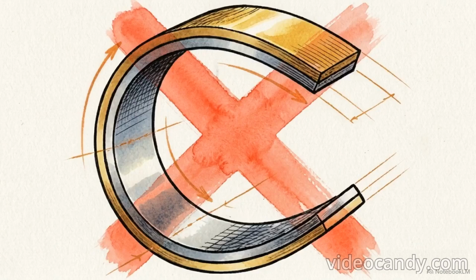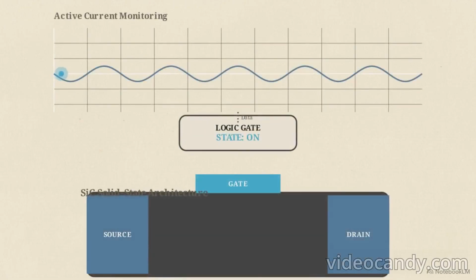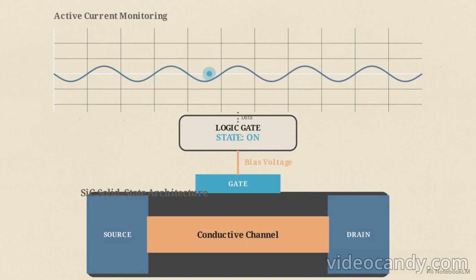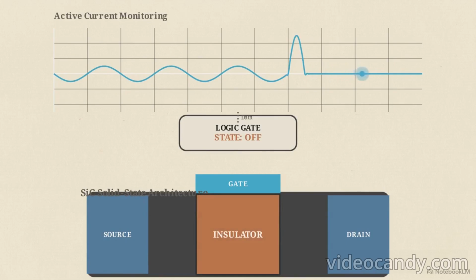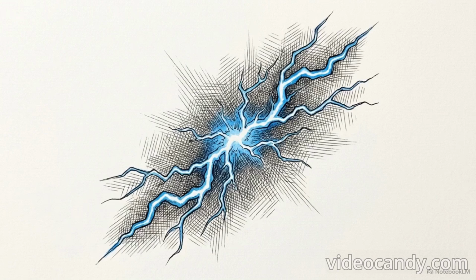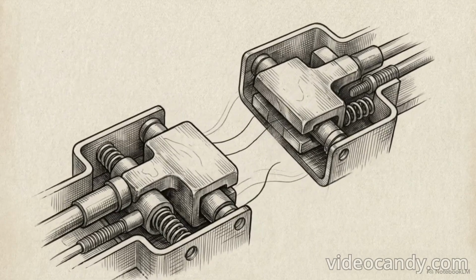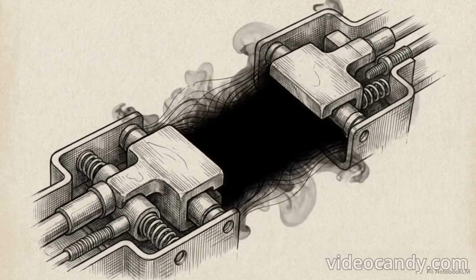Instead of waiting for a metal strip to bend, the E-breaker continuously monitors the active current using highly precise Hall effect sensors, or shunt resistors. During normal operation, an active bias voltage is applied to the semiconductor's gate terminal. This input creates an internal highly conductive channel, allowing the electrical load to pass through the silicon architecture seamlessly. The moment the sampling circuit detects the leading edge of a short circuit spike, the internal logic gate removes the bias voltage from the terminal. Without the bias voltage, the silicon channel instantly shifts from highly conductive to entirely non-conductive. There are no latches to swing or springs to release. The total interruption occurs in under 1 microsecond. This is thousands of times faster than any mechanical breaker, halting the current before an arc forms.